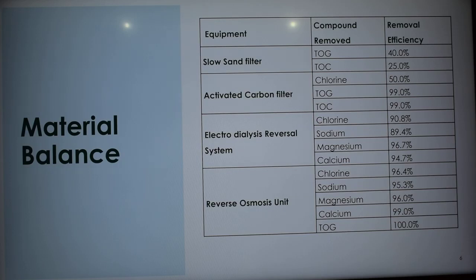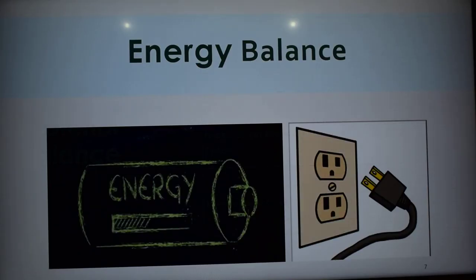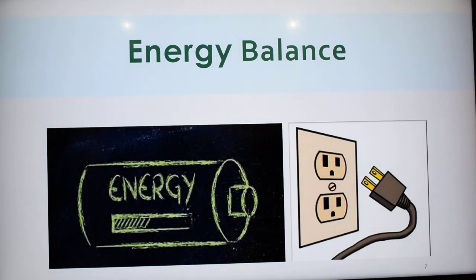So for slow sand filter, it removes TOG and TOC, which is total oil and grease and total organic content. Activated carbon filter removes chlorine, TOC and TOG. Electrodialysis reversal system removes chlorine, sodium, magnesium and calcium. And reverse osmosis unit we have for further reduction of the elements such as chlorine, sodium, magnesium, calcium and TOG.